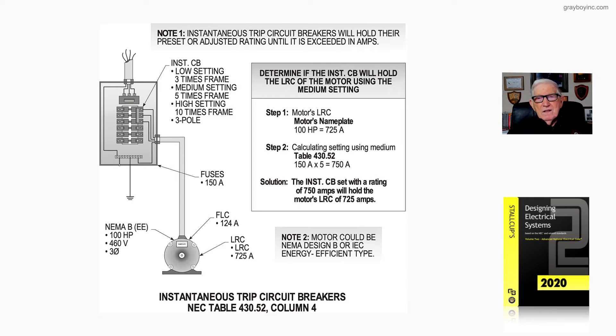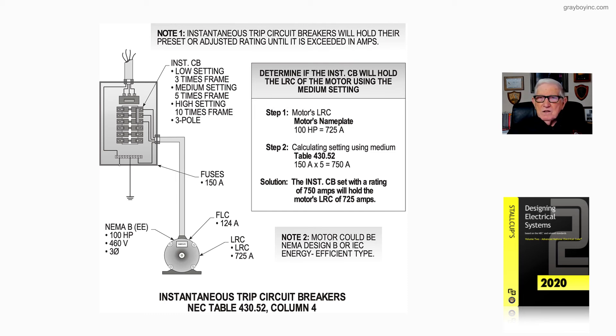Looking at Step 1, we have a motor lock-rotor current for 100 horsepower at 725 amps — that's what this motor could start at. Step 2: using the medium setting, five times 150 equals 750 amps. If the acceleration time of the load doesn't become a problem, that's going to allow the motor to start and accelerate the load. The instantaneous setting of 750 amps would hold the motor's lock-rotor starting current of 725 amps and would start the motor and drive the load, provided there's no acceleration period causing a problem.